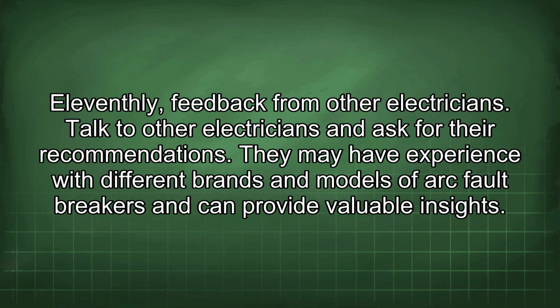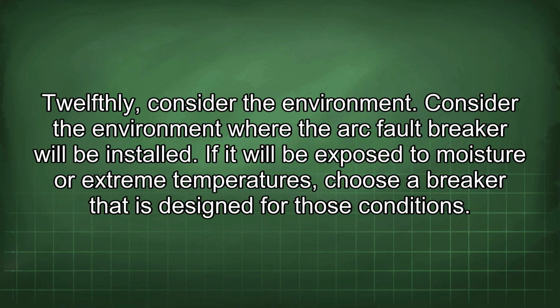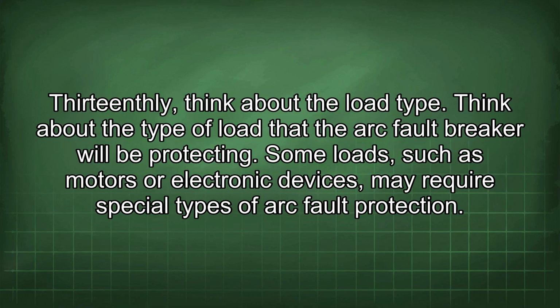11thly, feedback from other electricians. Talk to other electricians and ask for their recommendations. They may have experience with different brands and models of arc fault breakers and can provide valuable insights. 12thly, consider the environment. Consider the environment where the arc fault breaker will be installed. If it will be exposed to moisture or extreme temperatures, choose a breaker that is designed for those conditions. 13thly, think about the load type. Think about the type of load that the arc fault breaker will be protecting. Some loads, such as motors or electronic devices, may require special types of arc fault protection.